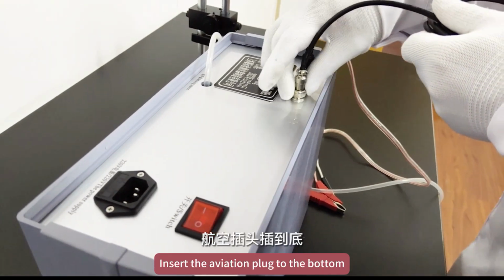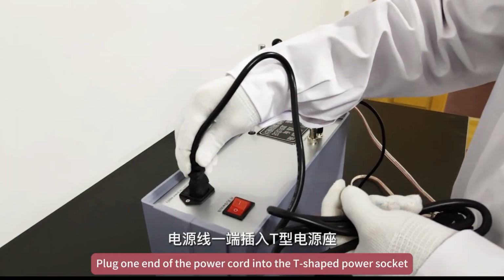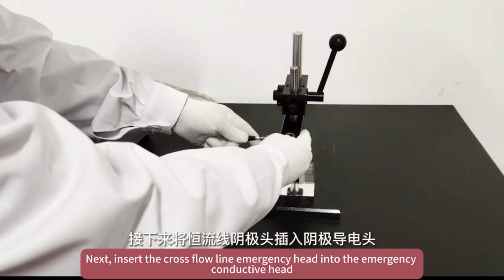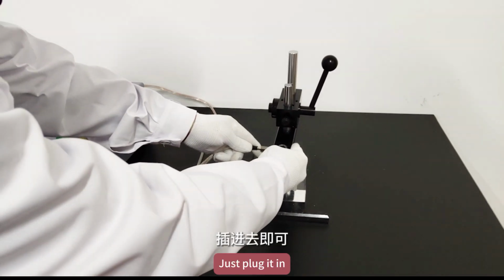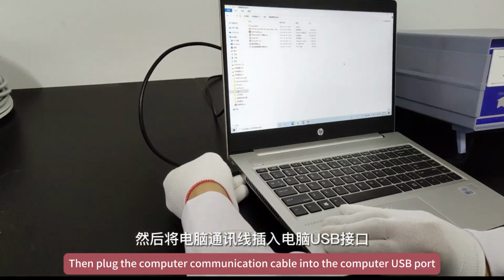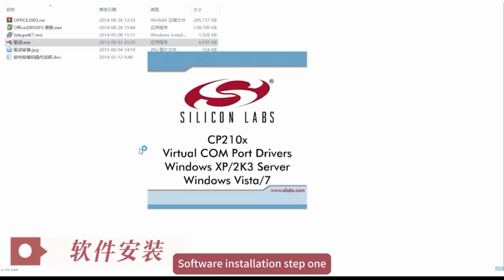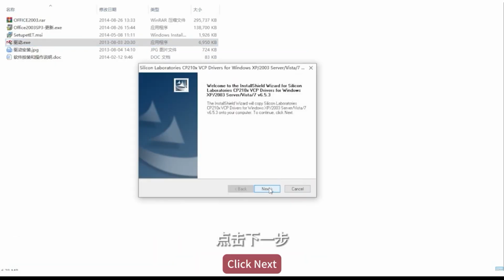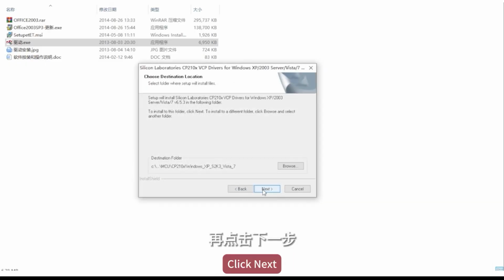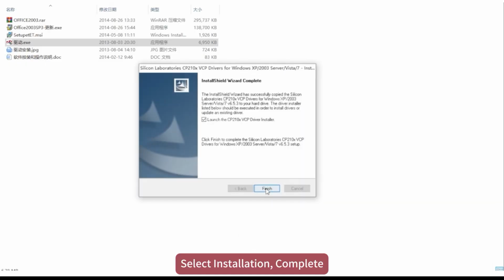Insert the aviation plug to the bottom. Thread locking. Plug one end of the power cord into the T-shaped power socket. Next, insert the cross-flow line emergency head into the emergency conductive head. Just plug it in. Then plug the computer communication cable into the computer USB port. Software installation step 1. Install the driver first. Click Next. Select the first. Click Next. Next step. Select installation complete.